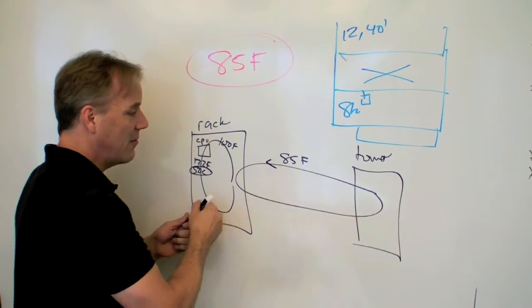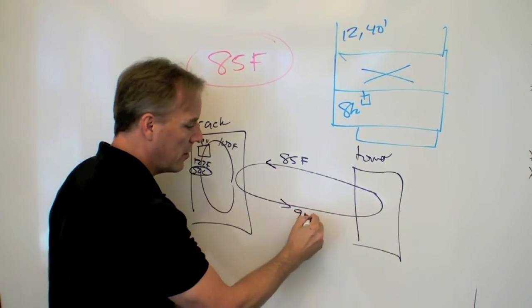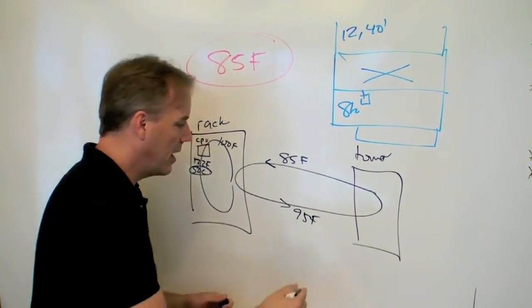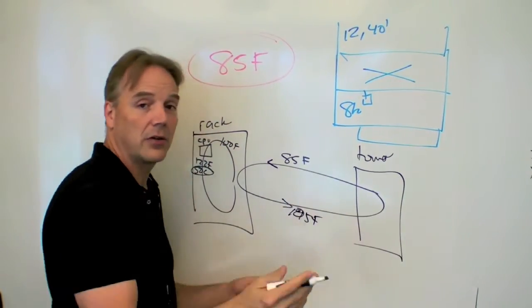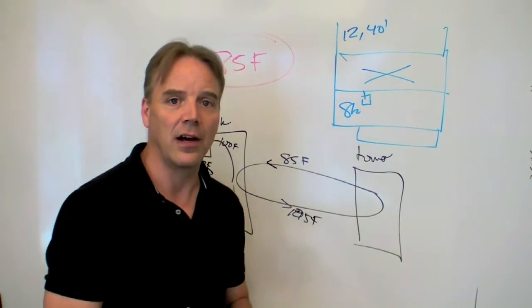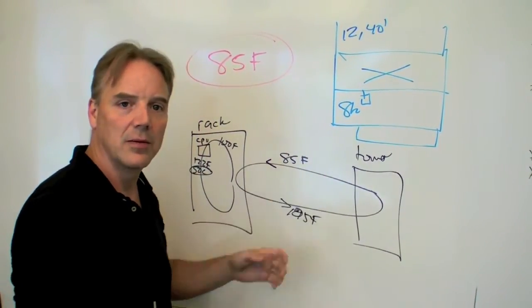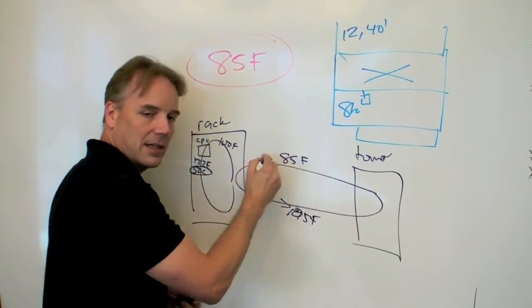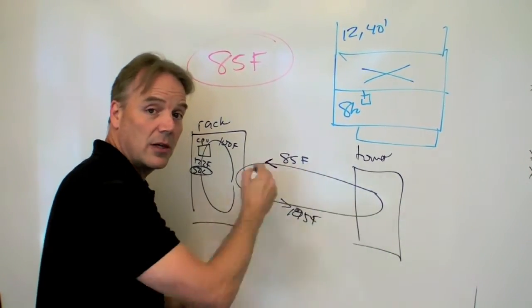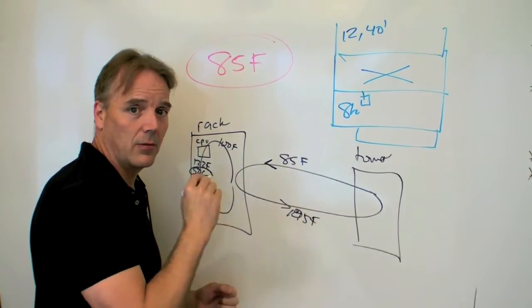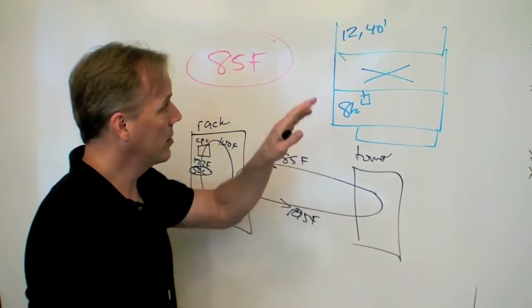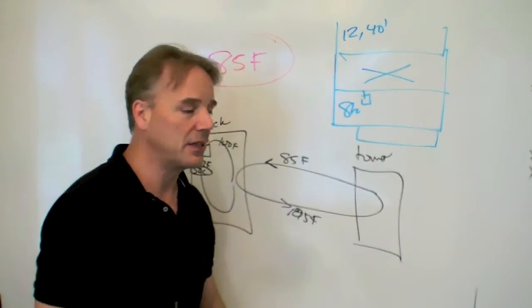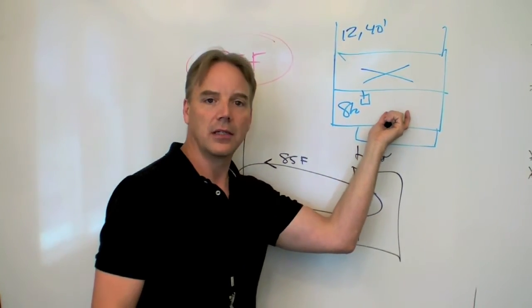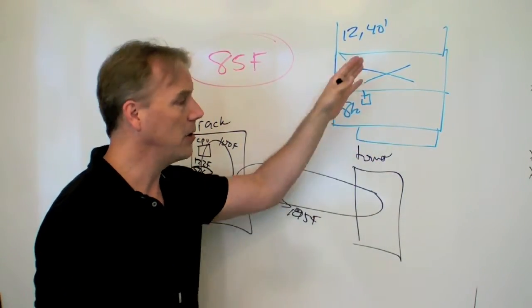So, 85 degree inlet, again, return whatever you think that would be. I'm just guessing it's a 10 degree rise. If it's 105 and a 20 degree rise, 30 degree rise, that's fine. Whatever you want to do for that efficiency. But the key is, how do I ensure I get that temperature coming in? This is next generation liquid cooling equipment that we're looking to be able to plug in here. Whether it's going to be a 40-foot container fully loaded on the top, or a pallet or a rack that rolls into here, I need the capability to be able to plug that in.